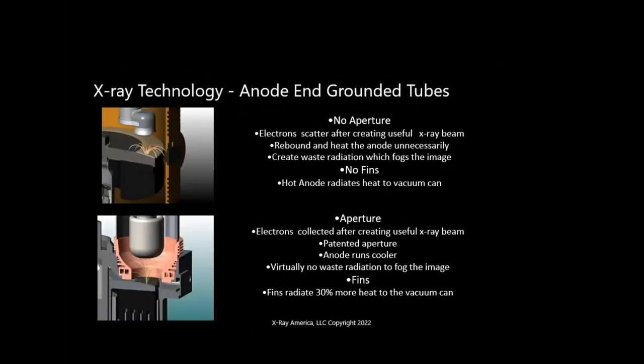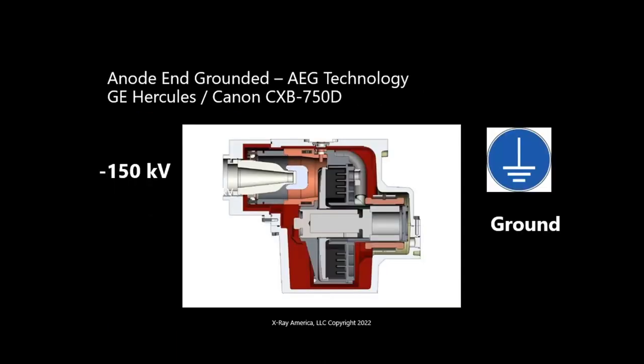So how this fits into the architecture of the tube, this is what an anode end grounded tube looks like in a diagram. You've got negative 150 kV to ground. Again, you've got your spinning anode, with techniques to cool the anode because you've got so much energy going. And this is that aperture. The rebounding electrons are caught here, and this has active cooling in these channels.